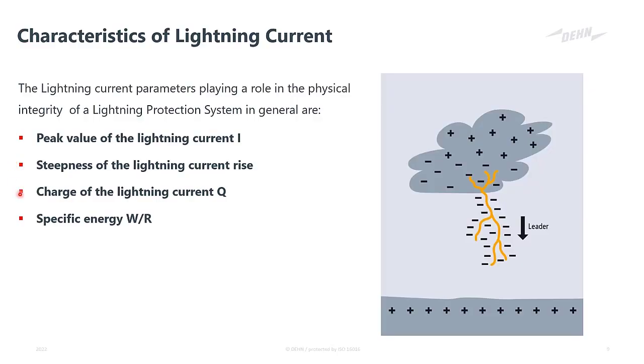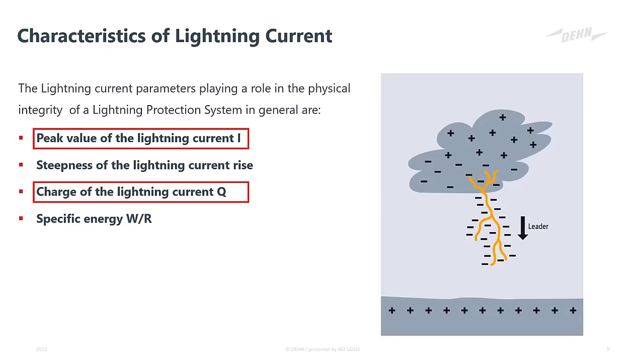The third one is the charge of lightning current. Lightning current carries high amounts of charge, and charge is responsible for energy conversion at a single point, so it would also be with regards to temperature rise. And then we have specific energy. Specific energy is the integral of the lightning impulse current squared, and this is responsible for heat distribution through a lightning protection system as well. Now, for the purposes of this webinar, we will focus on two main ones relating to wind turbines and wind turbine design, and that would be the peak value of lightning current as well as the charge of lightning current.